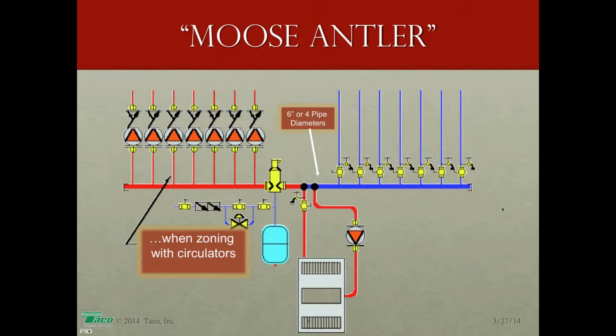This is kind of the same thing, only different, in that which one's the primary? Now, people will often refer to the boiler loop as the primary because you've got the supply port of the boiler going back to the return port of the boiler. Okay, that makes some sense. I can certainly see that.